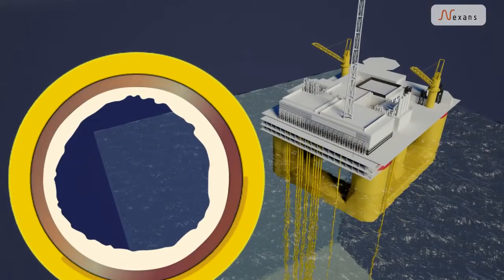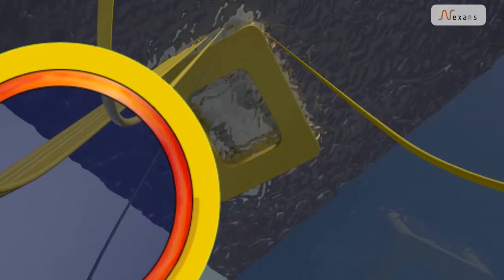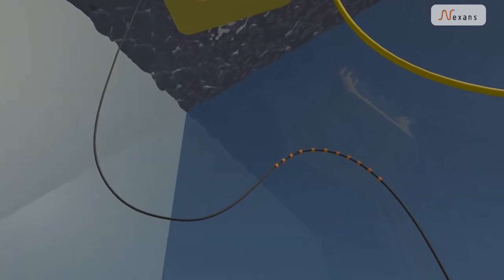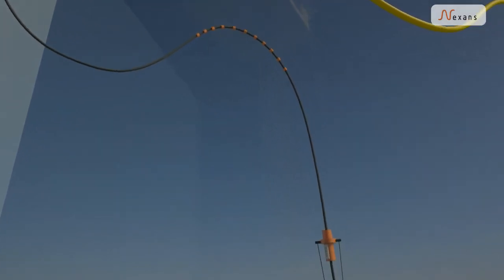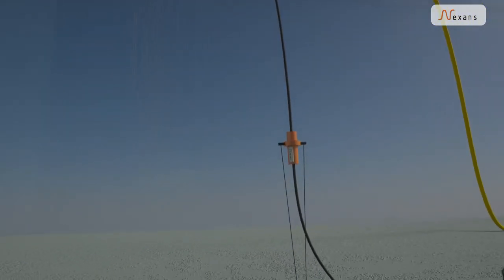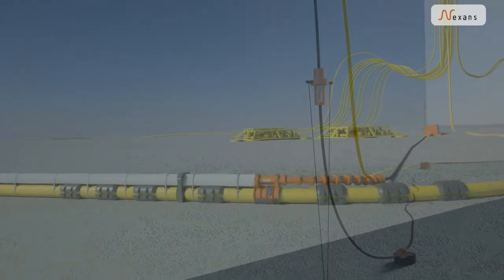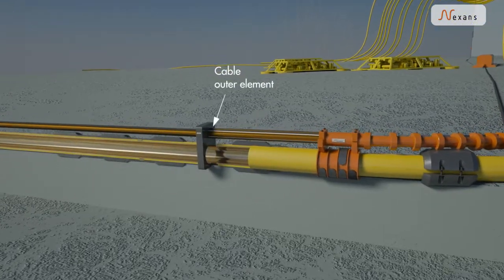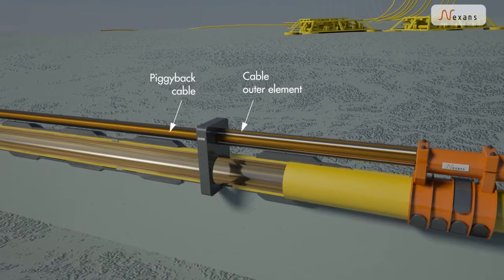The solution is called direct electrical heating — the pipeline itself is heated by an AC current. A high voltage riser cable is led down to a subsea junction box and further on to the pipeline near end, where the riser cable's outer element is connected to the pipeline.